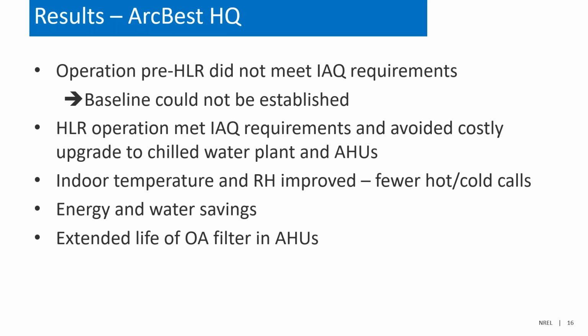But with the HLR operation, the building was able to meet the IAQ and thermal comfort requirements, and they avoided a costly upgrade to the chilled water plant and the air handling units. So the building owner had, as I said, the temperature and RH improved, so the occupants were very happy, which makes the owner very happy with the building, and they were able to save a lot of money on the chilled water plant upgrade. So this was a pretty big win for the building owner.